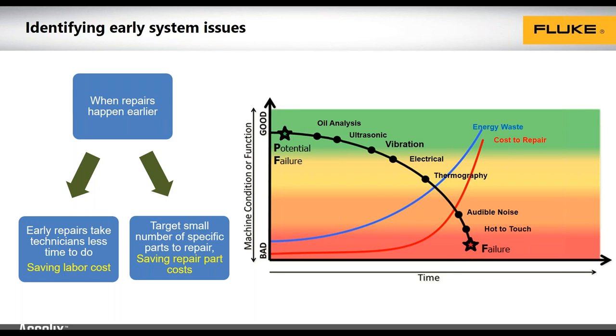When I was analyzing bearings in the Navy and working for a vibration consultant, we tracked using vibration — bearings would wear over an 18-month or two-year period, going from slight to moderate to serious to extreme over many months. That gives you plenty of time to plan. When you see it come up as slight, you don't run out and overhaul the bearing — you keep an eye on it. As it moves to moderate, collect data more frequently. As it moves to serious, schedule for the next downtime. When it gets to extreme, pull the trigger and repair, because letting it get too bad causes more damage.